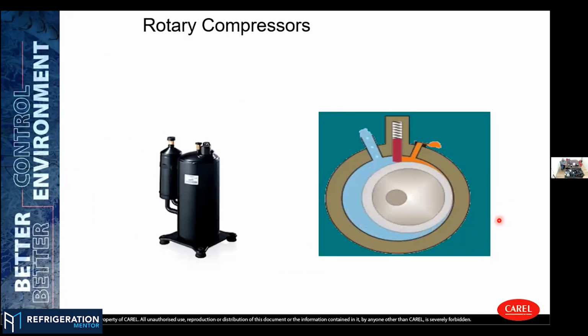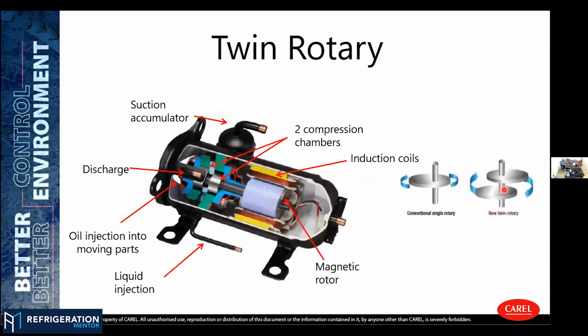So here is a very quick video just showing how a rotary compressor works. You have an inlet from one side, and we have this moving part on the inside that keeps in contact with the shell of the compressor chamber, making the compression. Here at this other slide, we can see a better view of the compressor inside. In this case, this is another type of compressor that has the liquid injection, as we mentioned, in order to cool down the discharge temperature when the superheat is very high or you are dealing with a very big delta pressure, so you will need it.